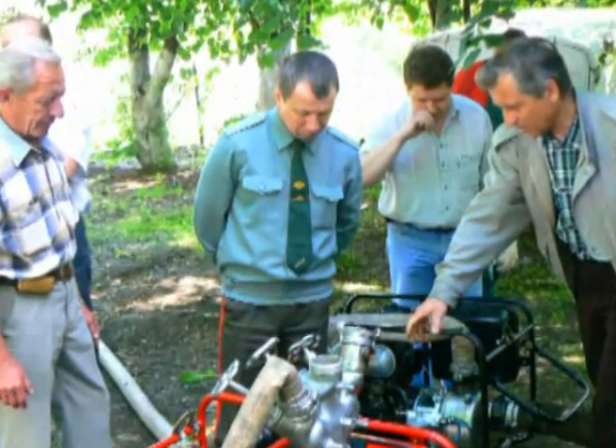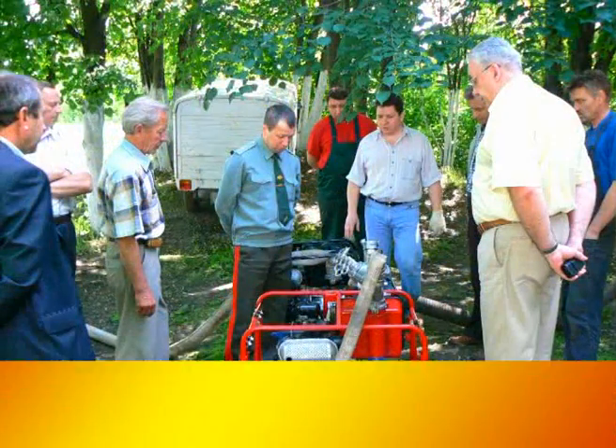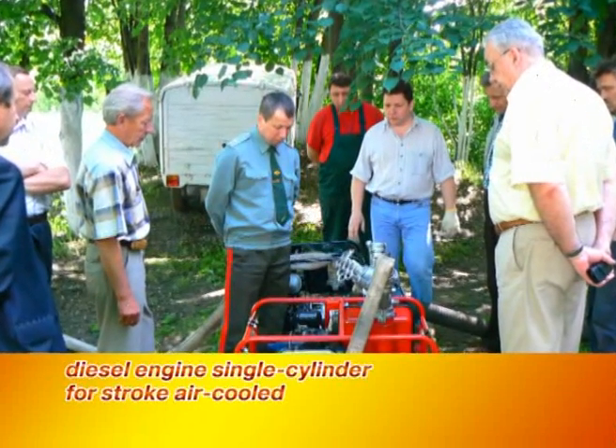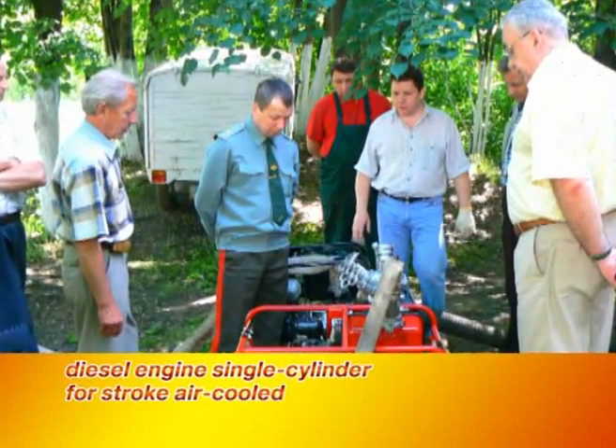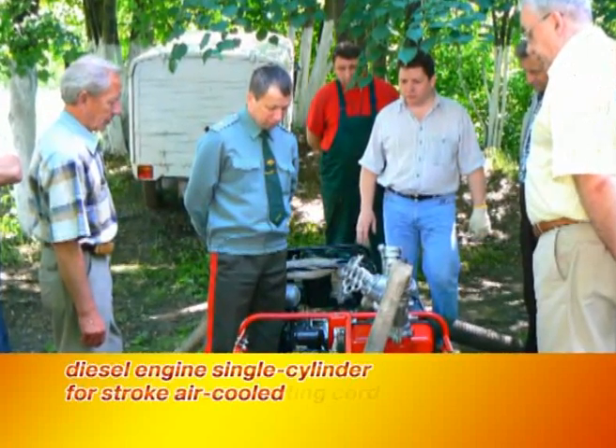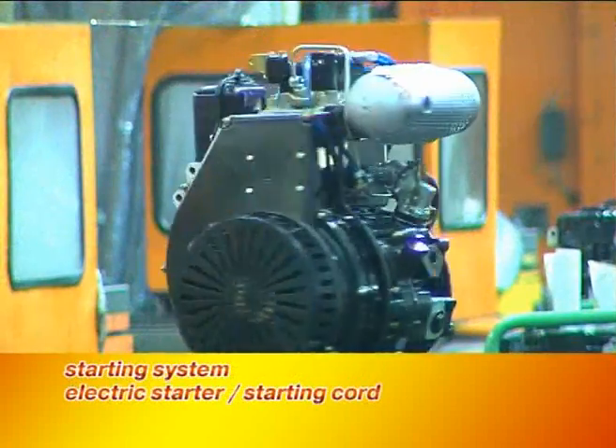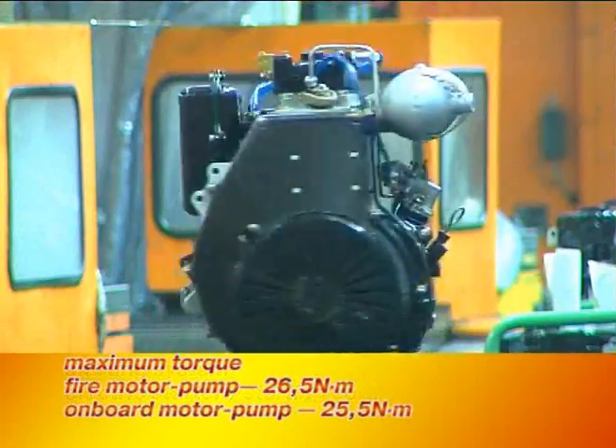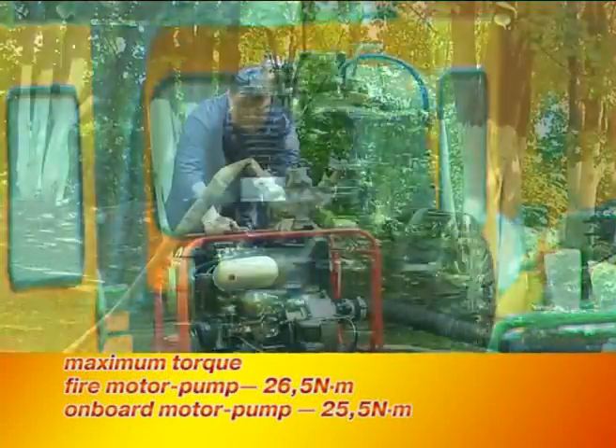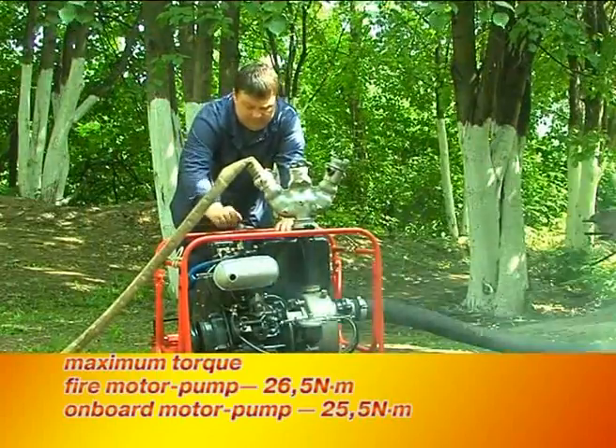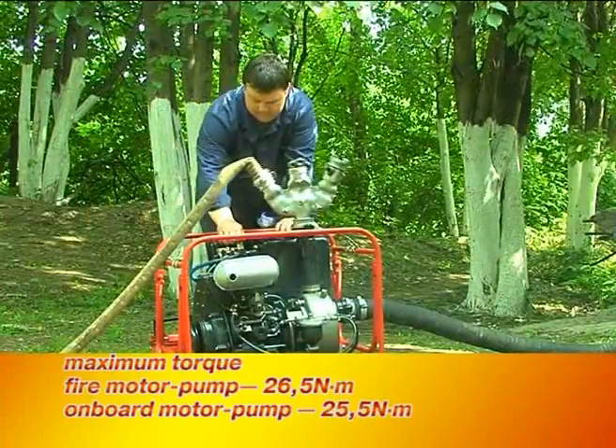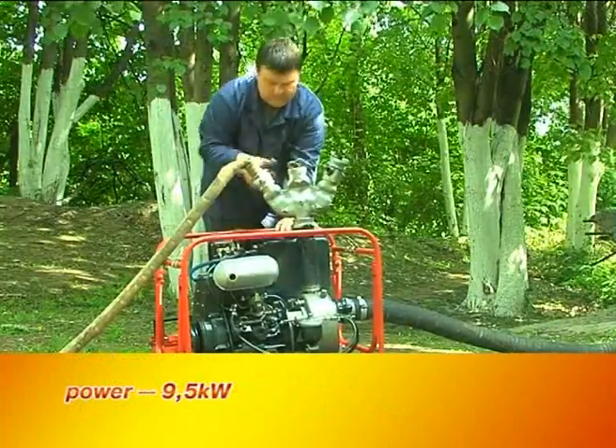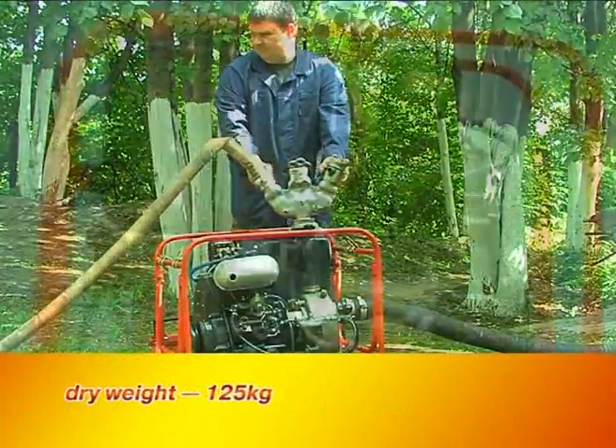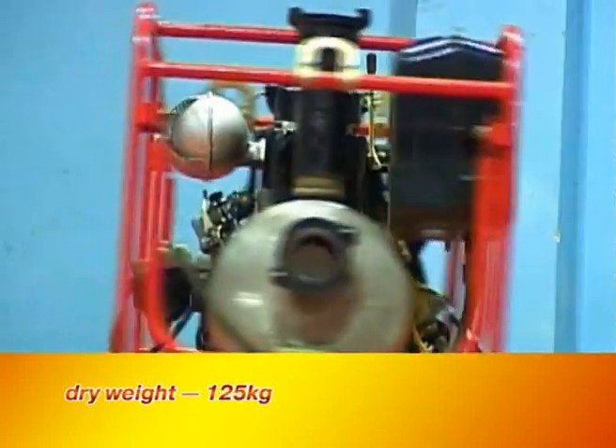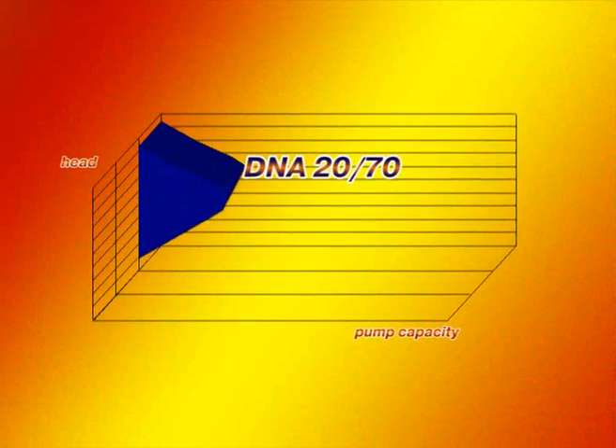Technical data of diesel engines included into presented motor pumps. Used in all the motor pumps is TMZ 520D single-cylinder 4-stroke diesel engine with air coolant. Starting system employs electric starter and manual starting cord. Maximum torque is 26.5 Nm for fire motor pumps and 25.5 Nm for onboard motor pump. Power is 9.5 kilowatt. Weight of the unit without completing components is 125 kg. Typical head capacity characteristics of presented motor pumps are given in the diagrams.